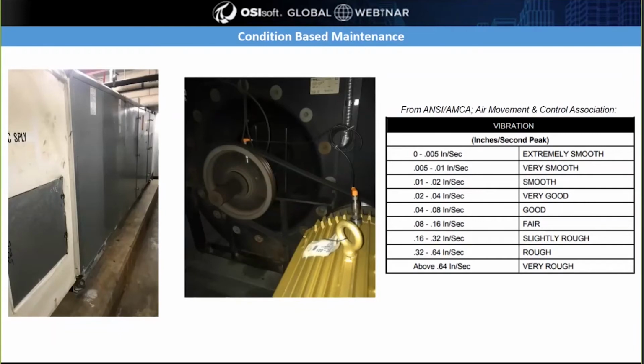To increase the reliability of this overall experiment, a condition-based maintenance project was deployed, and part of the project included monitoring vibration signatures. On the left-hand side, you can see just the air handler itself. In the center, you can see the fan motor, the fan belt, and the fan itself. You can also see vibration probes, and they have the little orange caps on top. There's one on the motor itself, there's one on the bearing that you can see at the near side, and there's a third vibration sensor on the far side, the second bearing of the fan shaft.